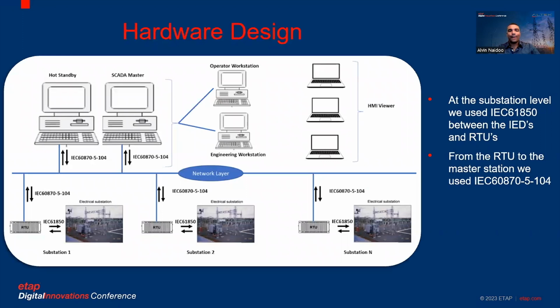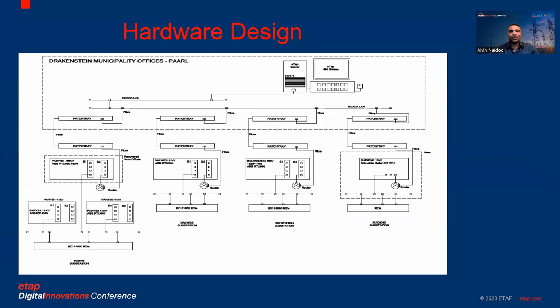As we can see, we've got the SCADA master station, we've got the hot standby, we've got the operator workstation, the engineering workstation, and we've got the HMI viewers. At the substation levels, we can see that we're speaking IEC 61850 between the RTU and the substation equipment. And from there, we're utilizing 60870-5-104 to speak to the master station. Here's what our design looked like with your fiber layout.